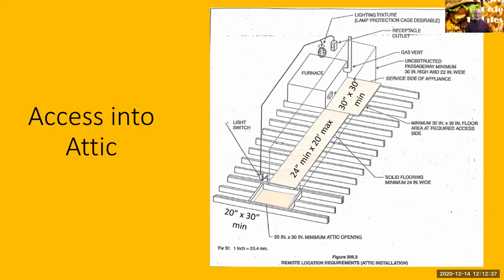And then a working area. The working area is still the same, the 30 by 30 platform. The reasoning we're showing this is because on retrofit, if you go in to make your quote and bid your job and it does not have this, it's your responsibility to figure this in your bid and put it in there. The electrical, if you're not a licensed electrician, the HVAC board won't hold you accountable for that. We might slide that to Charles over to the electrical side, but on the walkway and the platform, we will hold them accountable for ensuring that they can get a solid 2 foot wide walkway with a 30 by 30 working platform in front of that appliance.